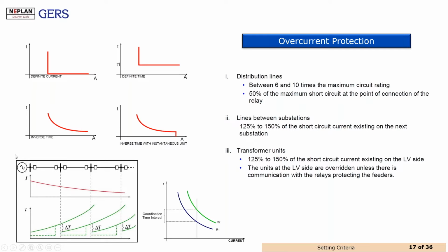It is notable how, depending on the fault location, we can set the overcurrent relays. And if we find proper settings, we will be able to provide some time delays between protections as primary and backup protections. Some standards recommend that the difference between the operating times be about 200 or at most 400 milliseconds. And getting this kind of time interval is one of the challenges for the coordination of the protections in the electrical systems.